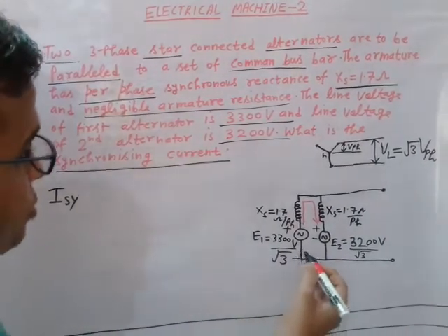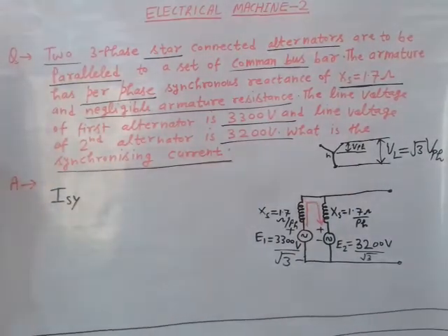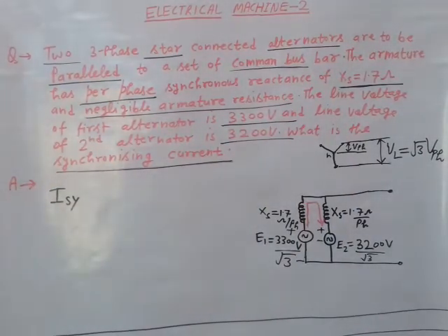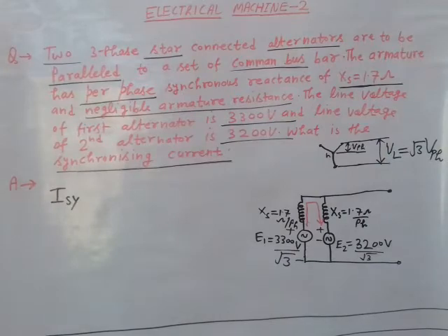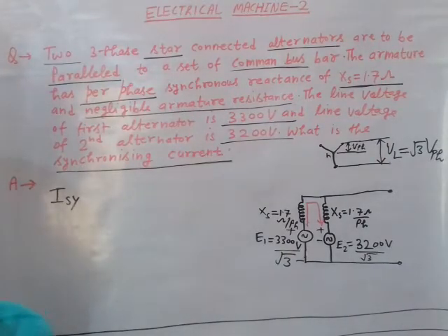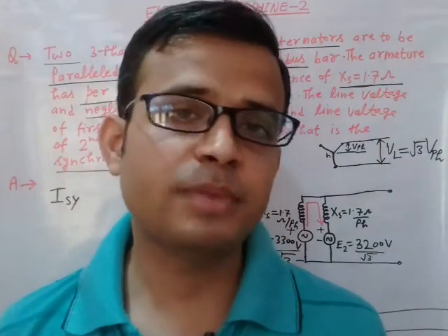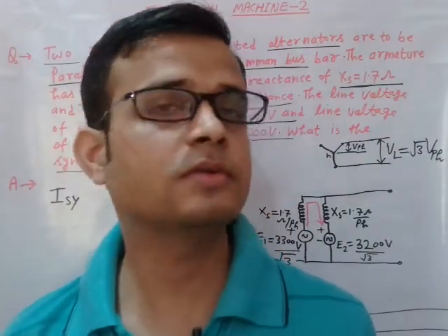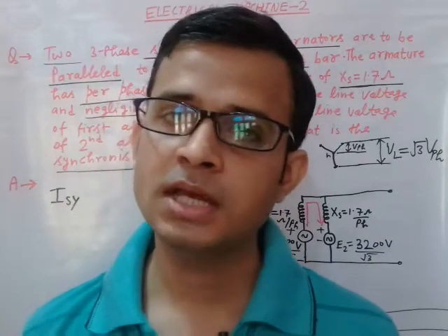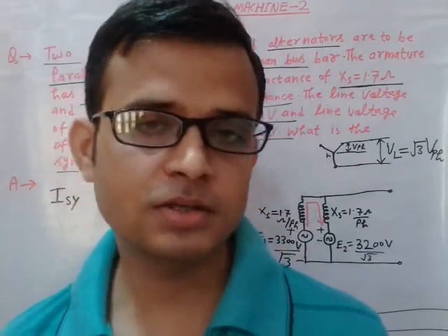You know alternators are synchronized at no load condition, when there is no load. At no load you will get the maximum synchronizing power. Synchronizing power coefficient is maximum at no load, and that's why the alternators are synchronized at no load condition.